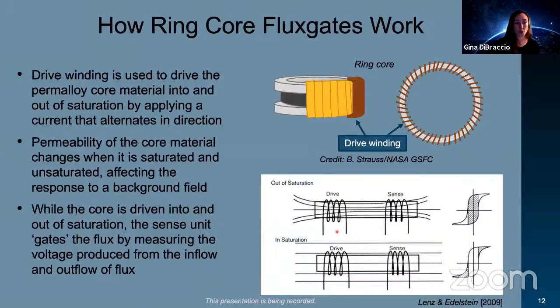There are two different scenarios: when the permalloy material is unsaturated at the top, and saturated at the bottom. We have these hysteresis curves that essentially show where the current is being applied. As I said, we're applying an alternating current to the drive winding, going in the positive direction, then coming down to the negative direction. For the top scenario, the shaded region is when there's very little current, or close to zero current, being applied.